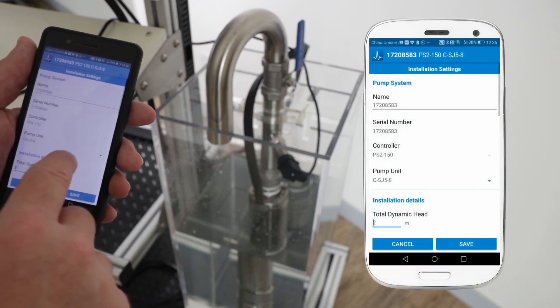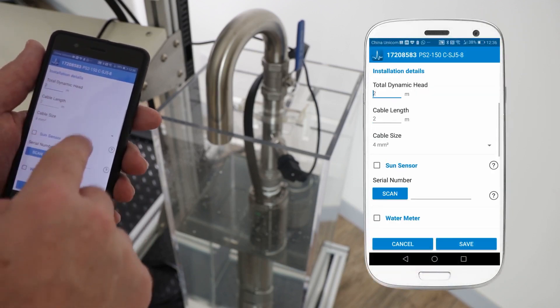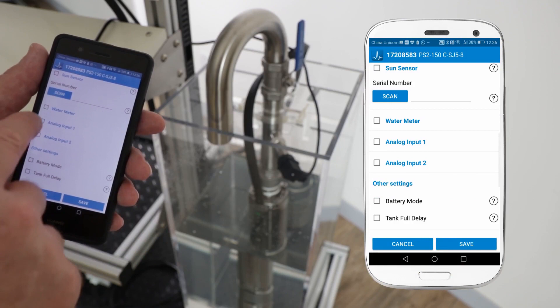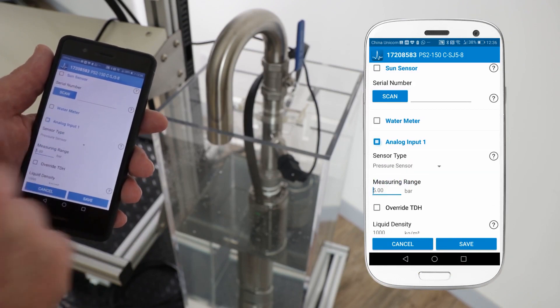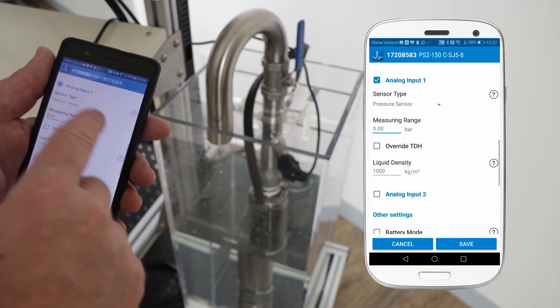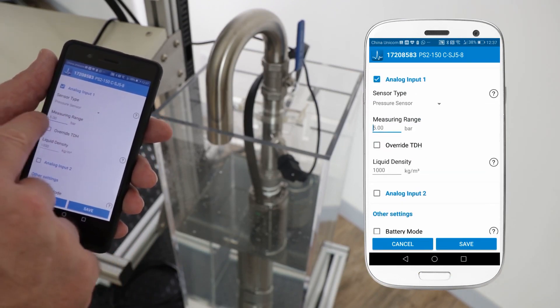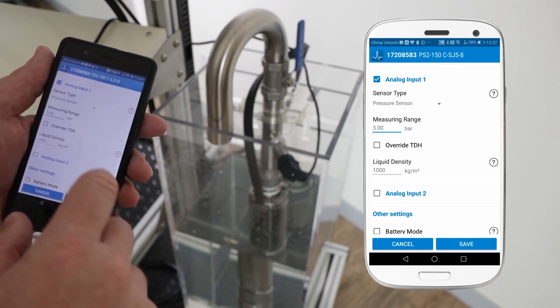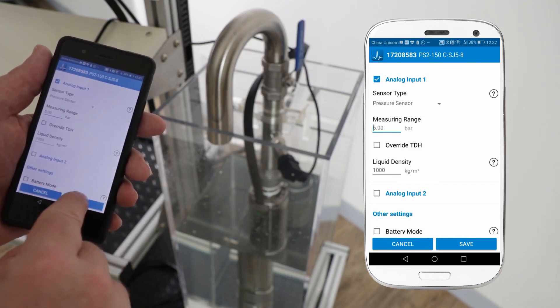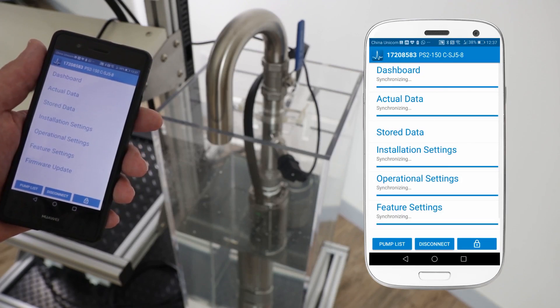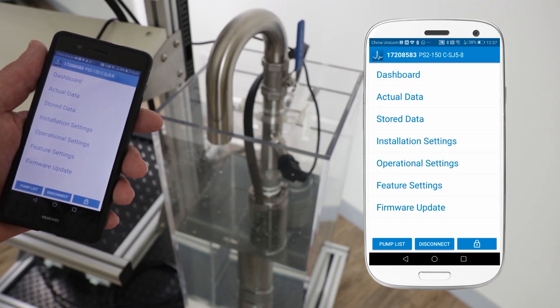I'm going to the installation settings menu, scrolling down to analog input 1 which is where we've connected the sensor. I'm going to select the sensor type as pressure sensor and in my measuring range I enter 5 bar and save settings. That's all the configuration complete.